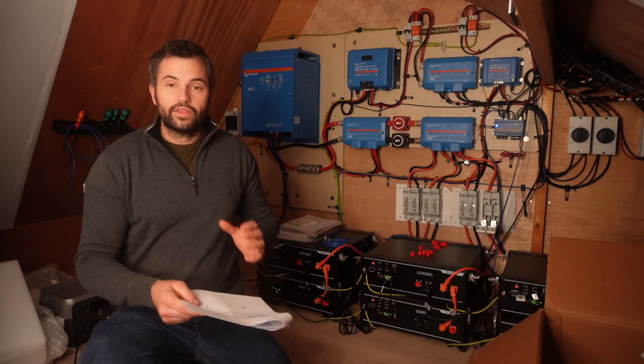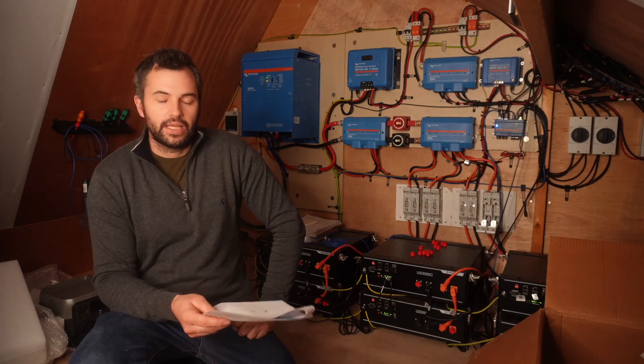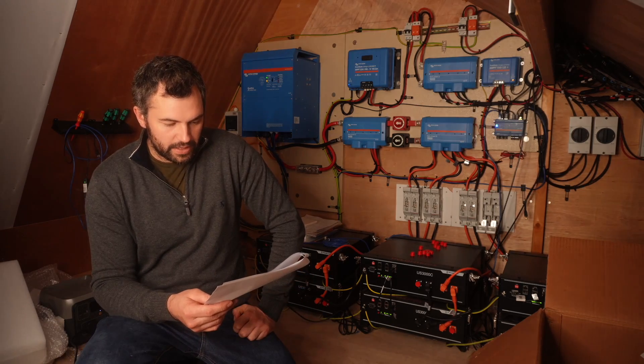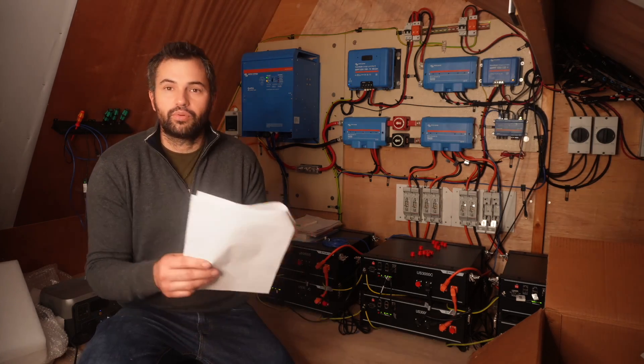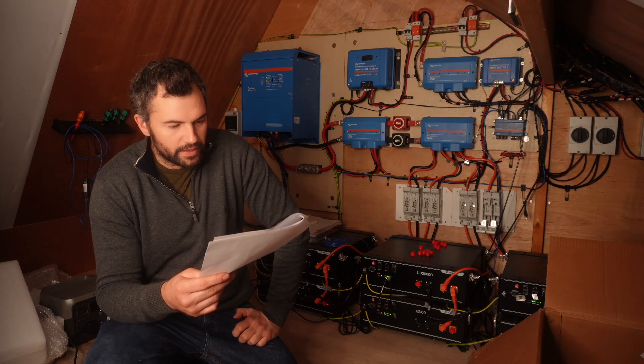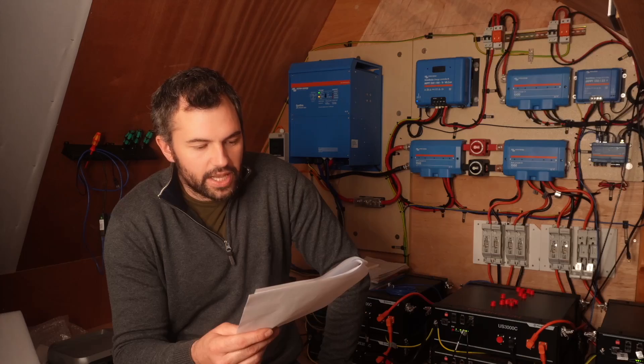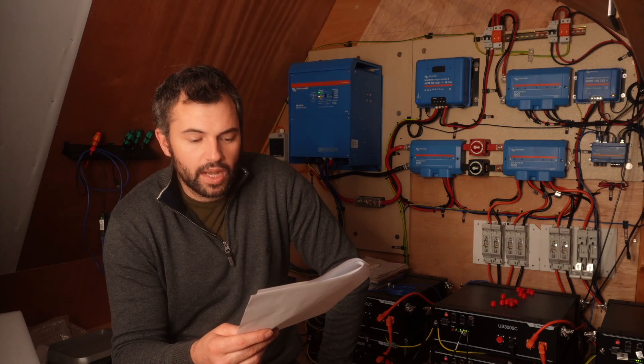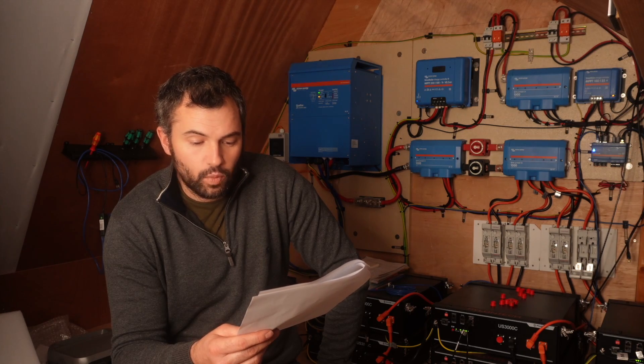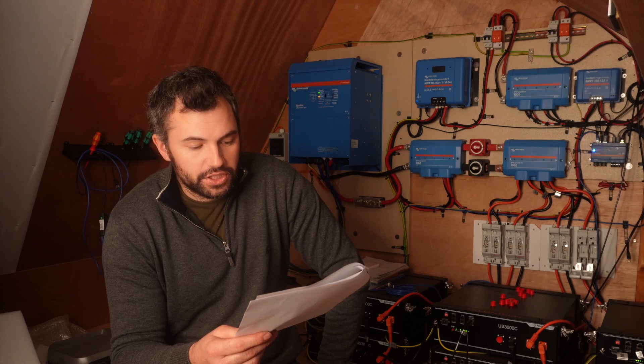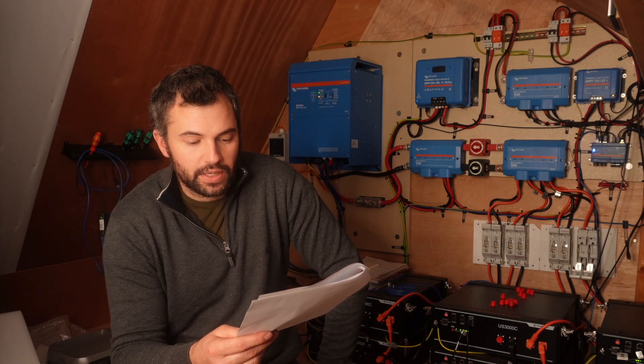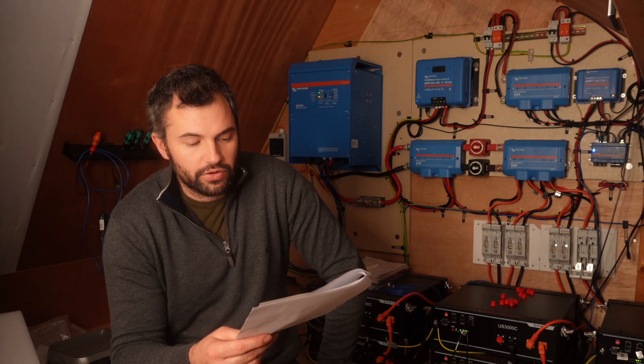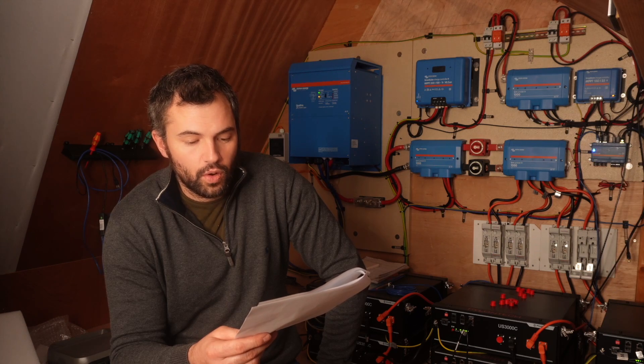So they've now fixed it, but the fault said fault could be cured with firmware update but replaced PMU/CMU board as a precaution. Now whether it was just a firmware update you can decide from the rest of this. It says extremely uncommon fault. Replaced board, uploaded newest firmware V1.7, charged battery fully, discharged under load, and trickle charge back to 100% at 2 amps over a few days to ensure the correct battery cell balance and operation.